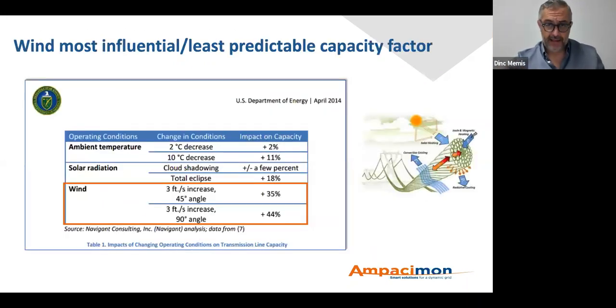My last slide is about what I mentioned regarding the wind factor. Of course, there are different weather parameters playing into dynamic line rating, such as ambient temperature and solar radiation, but the most important weather parameter is what we call effective wind, which is directly monitored on the conductor by a sensor. By effective wind we mean that the vibration and swing angle, measured by accelerometers, are converted to the effective wind, which is not only the speed of the wind but also the angle of the wind. That provides a significant, as you can see, 35 or 40% capacity improvement.